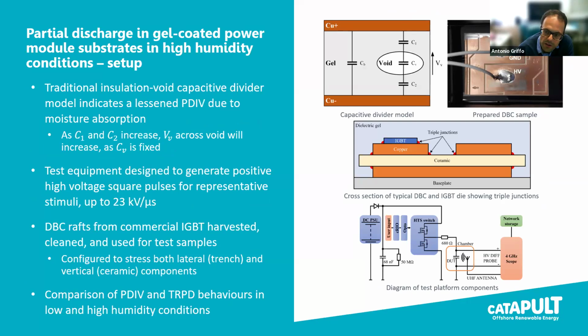One aspect that we are interested in understanding was whether the humidity creates a more favorable environment for the occurrence of partial discharge. Partial discharges are high energy discharge events that can occur within voids in the insulation, in the dielectric gel, and this can be caused by air bubbles or voids due to imperfect curing of the gel. When these voids happen at the triple junction, basically the conjunction point between the dielectric gel, IGBTs and the copper DCB, or copper and ceramic substrate, this is where the partial discharge has the potential to create treeing into the dielectric gel and damage it, and longer term create a cumulative effect that can lead to the failure of the insulation properties.